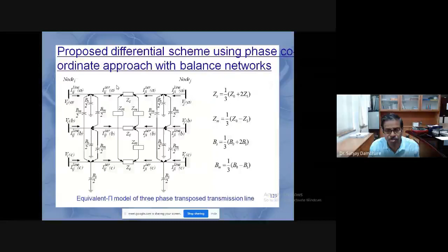The scheme can also be made adaptive, because the restraint area can be small and acceptable for high resistance faults. High resistance faults will not need a larger restraint area, while a larger restraint area is required for low resistance faults. So the question is, can you make this restraint area a little bit adaptive?